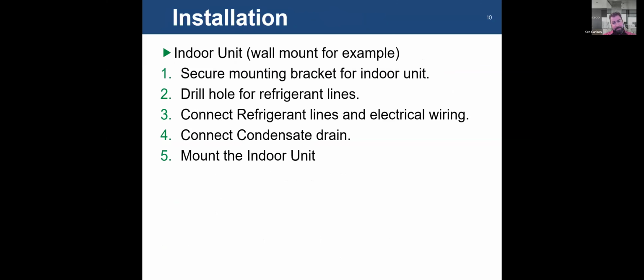So we're going to jump right in. Taking a wall unit, for example, a heat pump like a mini split, just because it's one of the most common installations that are out there. Many different options, very versatile. You're setting your indoor unit. You've got to secure a mounting bracket. You've got to drill your hole to get your refrigerant lines, drain, and power from that unit to another place, typically outside. You've got to connect your refrigerant lines and condensate drain, and then you'll mount your indoor unit.